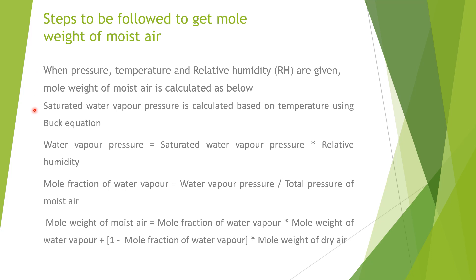First of all, saturated water vapor pressure is calculated based on temperature using the Buck equation. Once saturated water vapor pressure is calculated, water vapor pressure is calculated, which is equal to saturated water vapor pressure multiplied by relative humidity. Then mole fraction of water vapor equals water vapor pressure divided by total pressure. Then molecular weight of moisture equals mole fraction of water vapor into molecular weight of water vapor, plus (1 minus mole fraction of water vapor) into molecular weight of dry air.